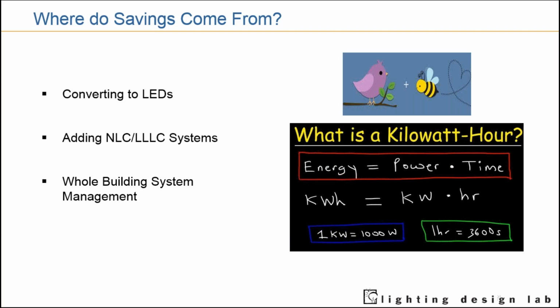When you add network lighting control systems, you do a little bit of both. You definitely reduce the wattage with strategies such as personal control or high-end trim, what we're going to review in a moment, but you'll more so impact the system by reducing operating hours, turning off lights when people are not in rooms, or leveraging natural light. Ultimately, the most powerful tool when it comes to savings is interoperability - tying in your phantom loads, your plug loads, tying in the different HVAC set points. So again, network lighting controls can serve to be that infrastructure to combine savings.